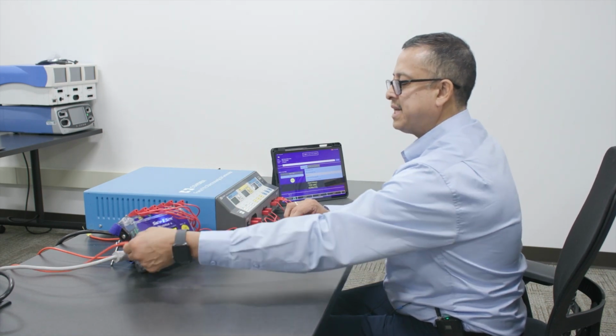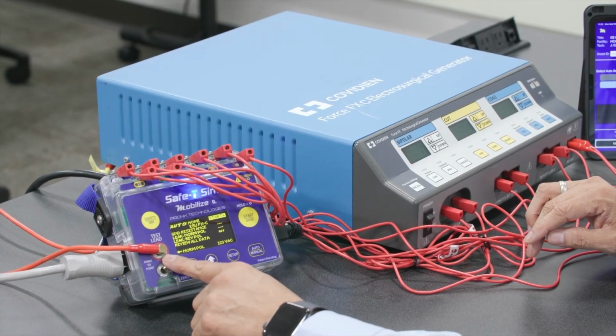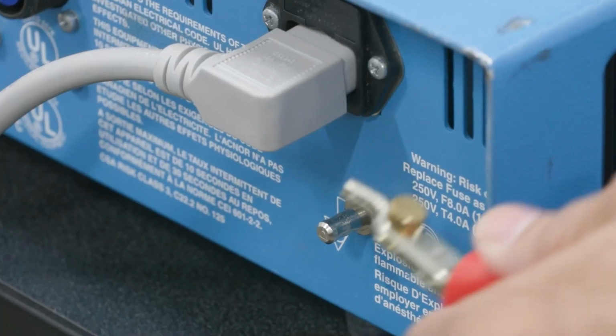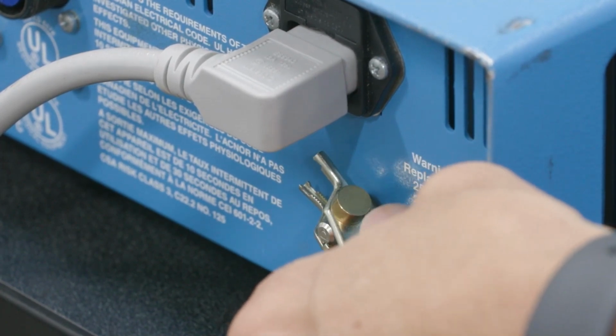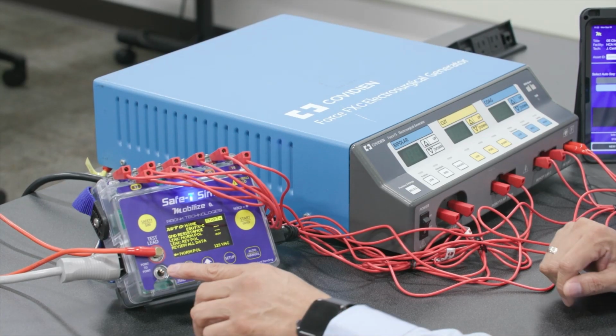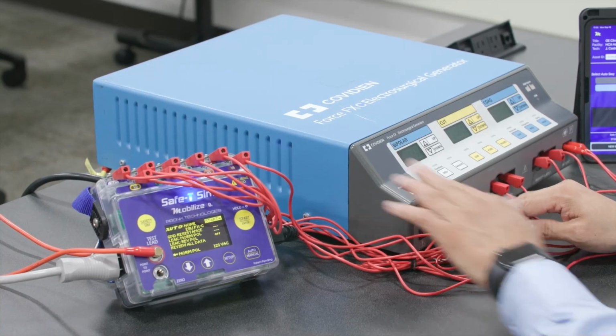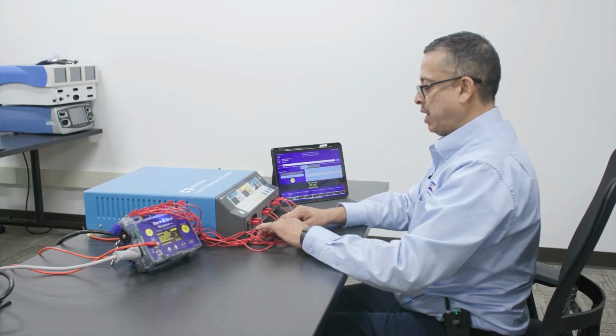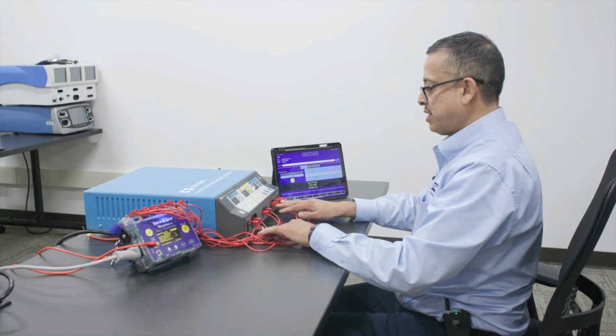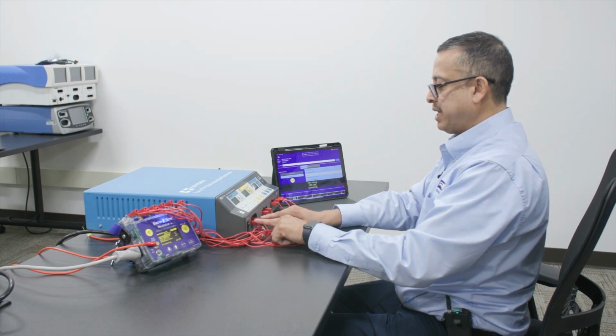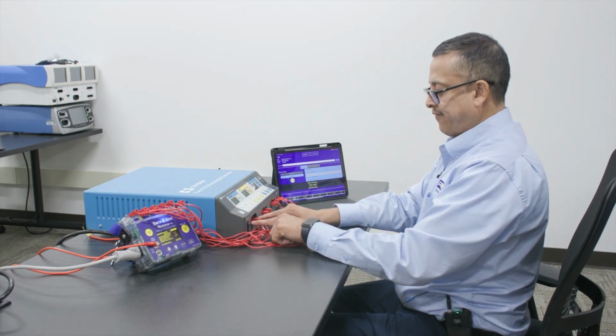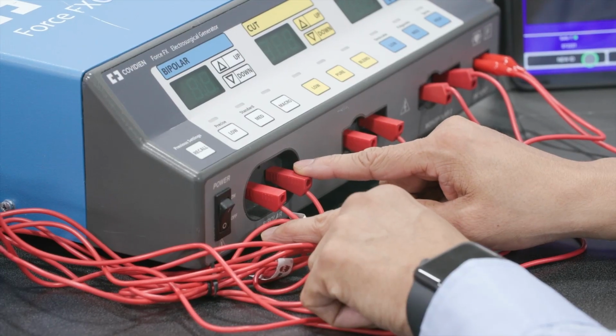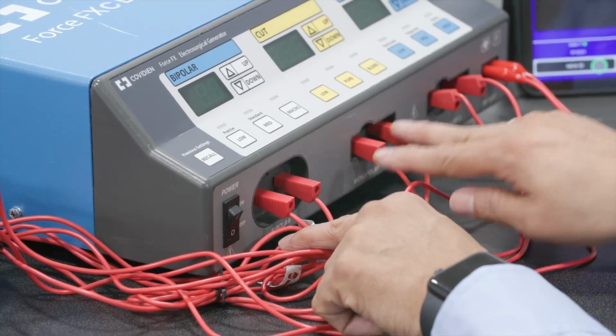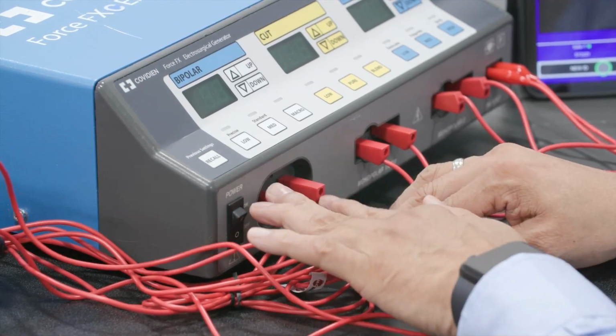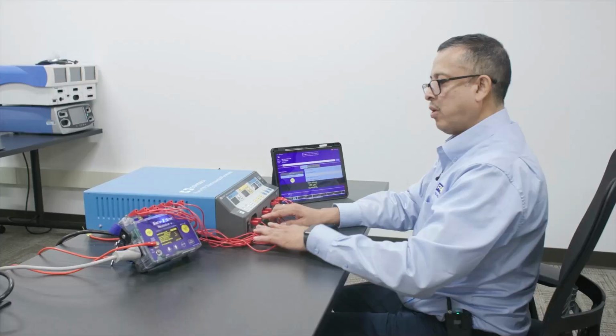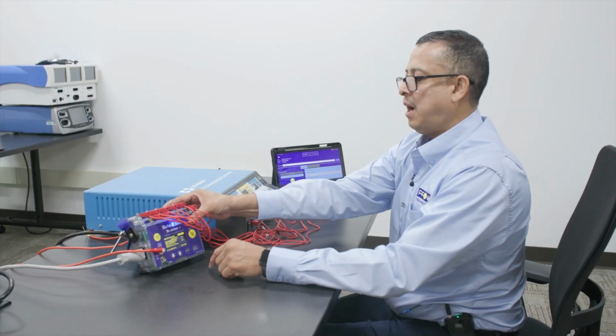You want to take the red test lead cable, make sure it's plugged into the upper jack of the safety sim, and connect it to the ground post in the back of the Force FXC. And now we also want to connect our outputs to the safety analyzer. And you want to do that for all 3 of the ports. And you want to do it by making sure you're connecting your test leads to the far left port and the far right port, the outer ports, on each one of these channels. So you connect these red leads from the output port over to any of the snaps on the safety sim.